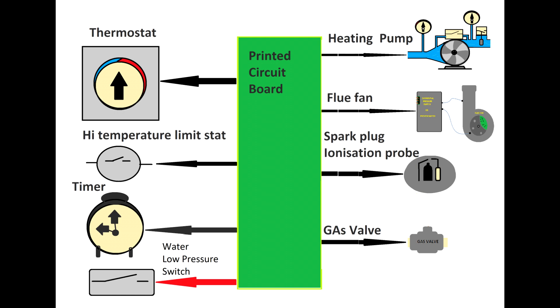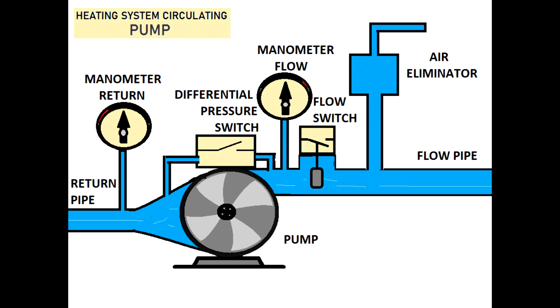The boiler startup protocol goes like this: first it will check if the water in the system is okay, then if the high temperature limit switch is okay, then the thermostat and timer will call the system to run. The pump will start first, and if the pump is healthy and running, then the flue fan will start to purge the system. Then ignition begins — the spark plug is initiated, then the gas valve opens, and then the ionization probe reads the information. In a domestic application you will only have a flow switch telling you that water is circulating.